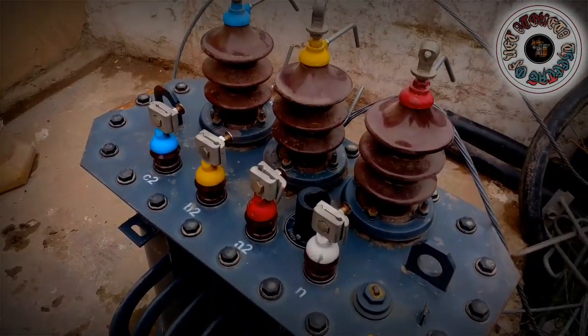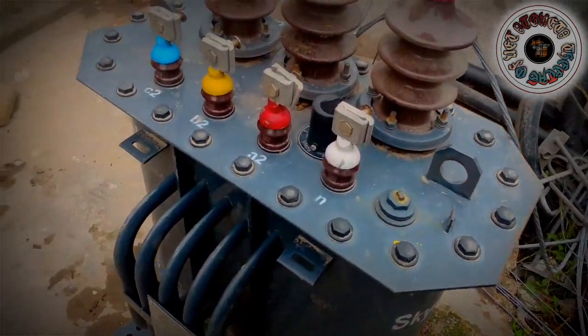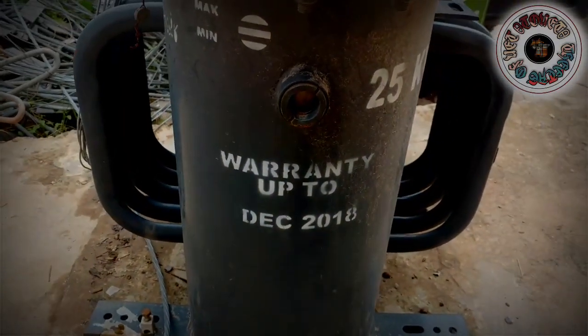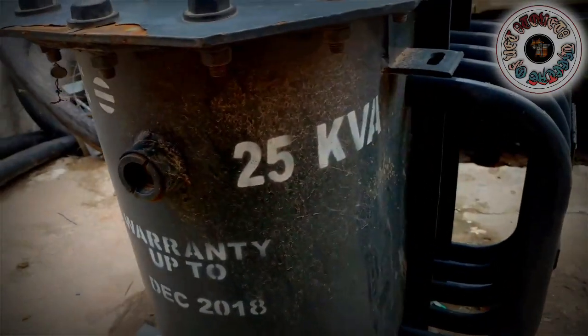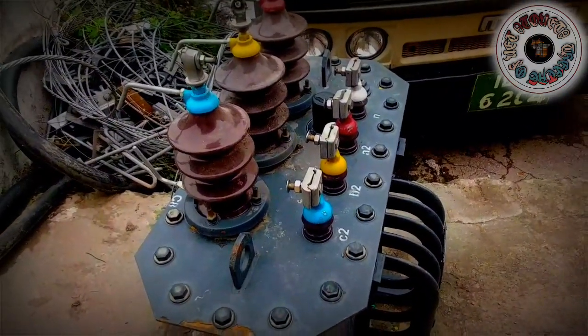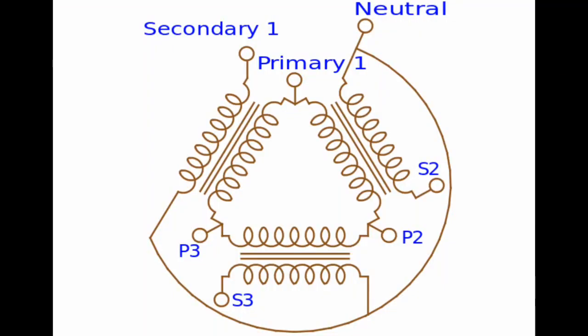In the secondary you can see there are four terminals, meaning the output is in Y connection. It is necessary to convert to Y because all the electricity we use in our homes is in Y connection. Here is the circuit diagram of the transformer — the primary is in delta while the secondary is in Y connection, with three coils where one terminal of each coil is connected together to form a neutral, and there are three phases.